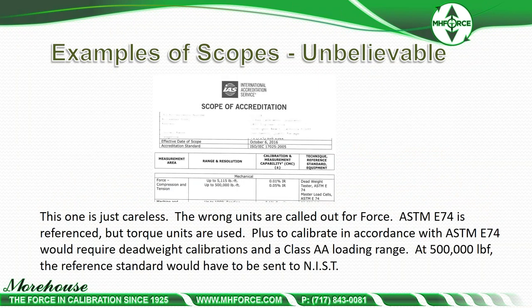Here's one that is just careless: the wrong units are called out for force. They say they do deadweight E74, but if you look over here, they're citing 'pound-feet' — which is torque, not force. They claim to do E74 calibrations with master load cells, but they're saying 'pound-feet.' To calibrate in accordance with ASTM E74 at half a million pounds would require deadweight calibrations in the Class AA loading range, meaning the reference standard would have to be sent to NIST. I know who this lab is — they're not sending their standards to NIST. This is a garbage scope, and shame on the auditor for not picking up the wrong units.